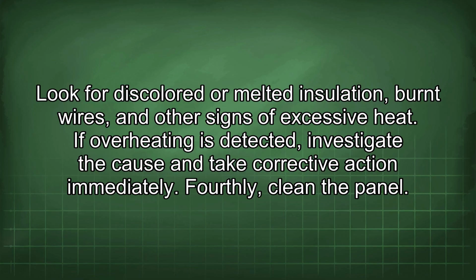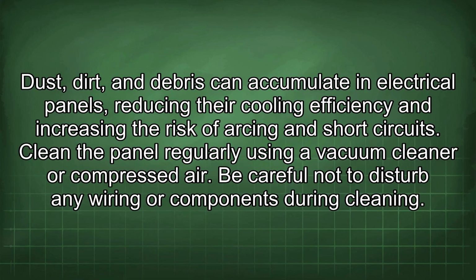Fourthly, clean the panel. Dust, dirt, and debris can accumulate in electrical panels, reducing their cooling efficiency and increasing the risk of arcing and short circuits. Clean the panel regularly using a vacuum cleaner or compressed air. Be careful not to disturb any wiring or components during cleaning.